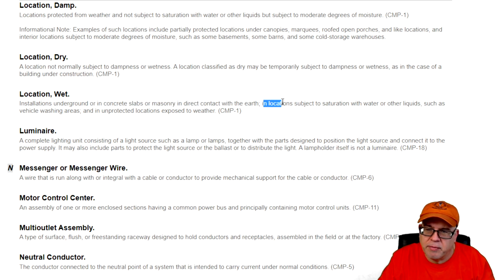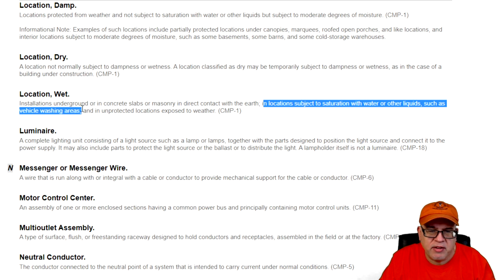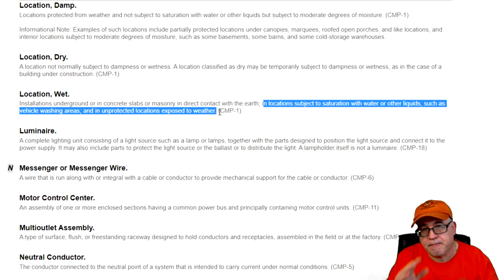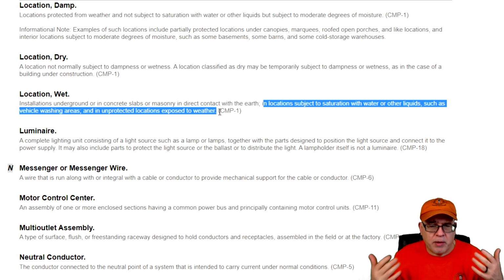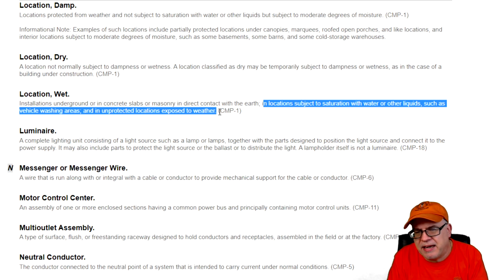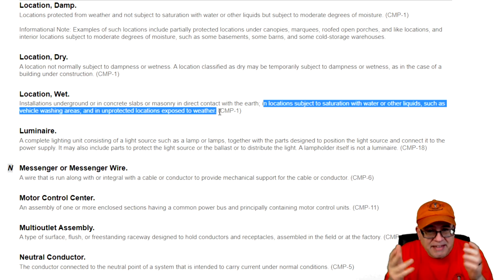It says, in locations subject to saturation with water or other liquids, it's not just water, such as vehicle wash areas and unprotected locations exposed to the weather. So outside, if it's exposed to the weather, that's a different thing. The difference between a wet and a dry is that in the wet, it's expected to be always exposed to this potential for this condition. The dry application allows for temporary dampness or wetness, not submersion, not total saturation. It's just wetness. Another example, I took a piece of wire and I sprayed some water on it. It's just wetness. It's going to end up drying, and it's going to end up in a location that, when it's all done, is a dry location.